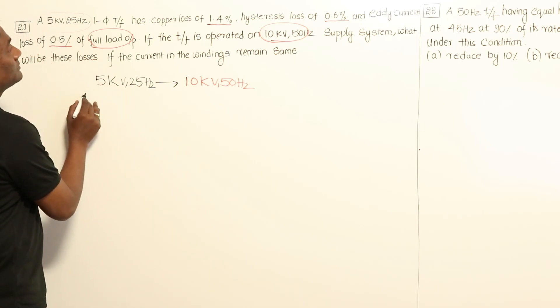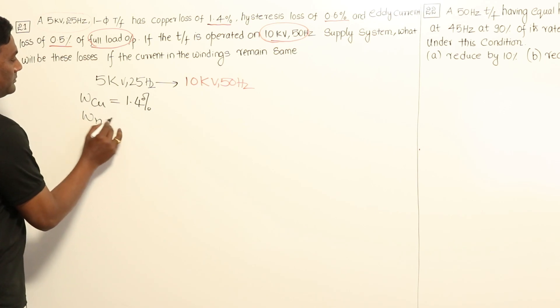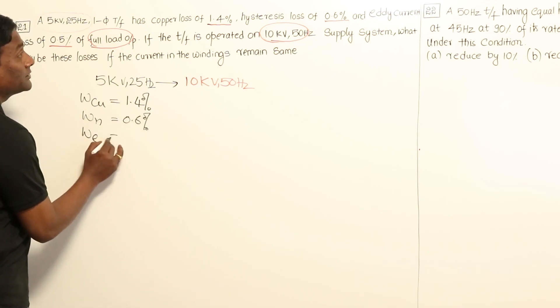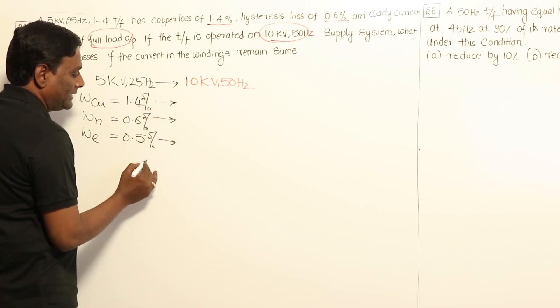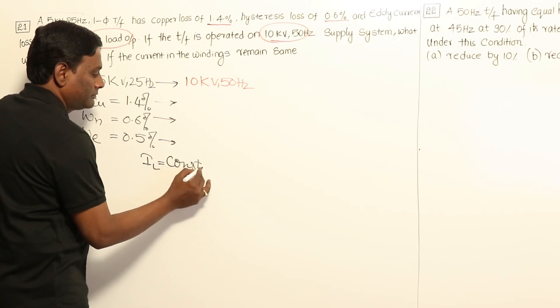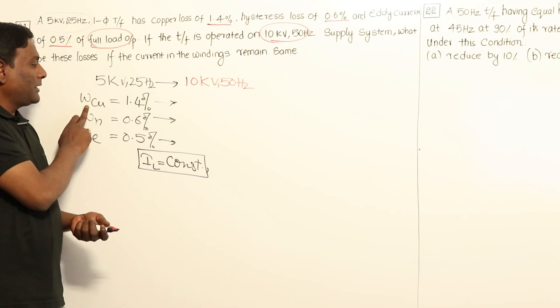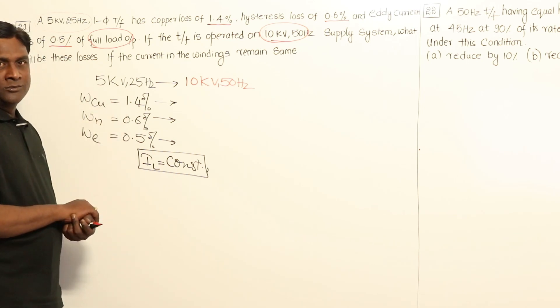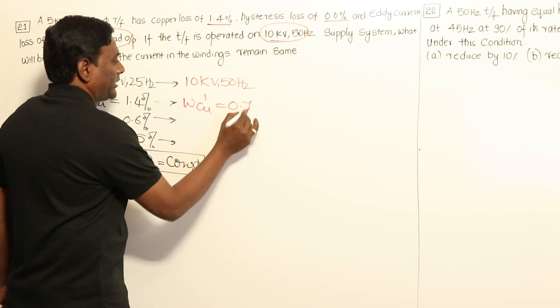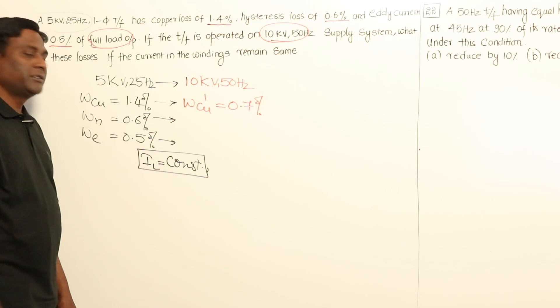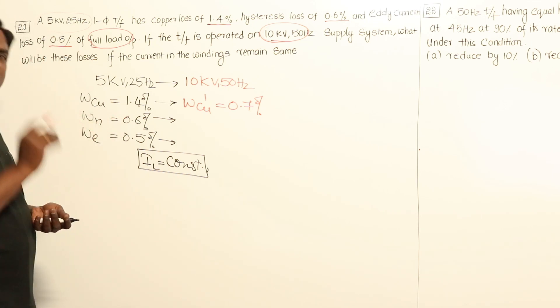In the first case, copper losses are 1.4%, hysteresis losses 0.6%, and eddy current losses 0.5%. Now, how do these losses vary when the current in the windings remains the same? Since copper losses depend on current and current is the same, copper losses in watts remain the same. So the new copper losses become 0.7% — the actual watts are the same but the percentage changes.